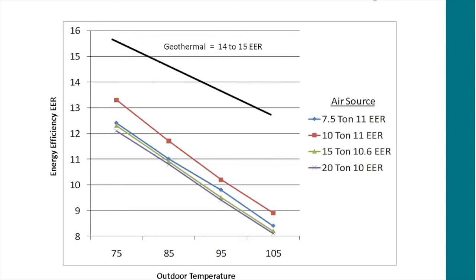So now instead of expressing it in COP, the air source heat pump industry uses a new term, the heating seasonal performance factor. What the heck is that? It's COP. They come up with a new term that totally rigs the rating system to their benefit. From a national perspective, we need to rethink how we rate equipment, we're letting it get away from us, and people are using it against our industry.